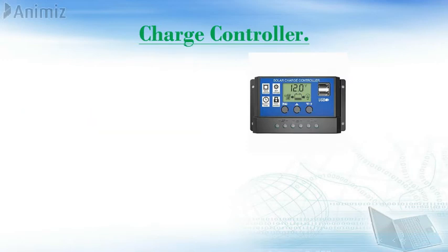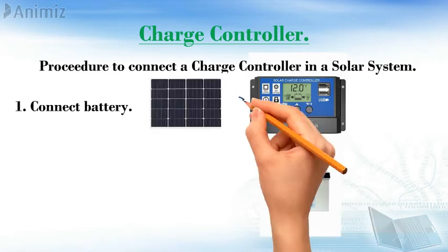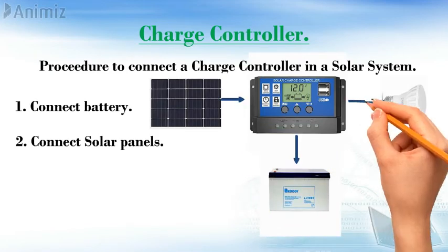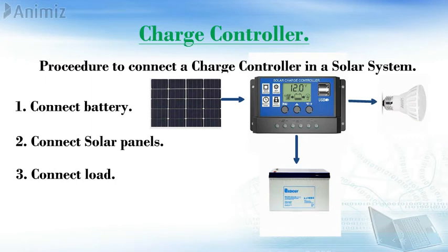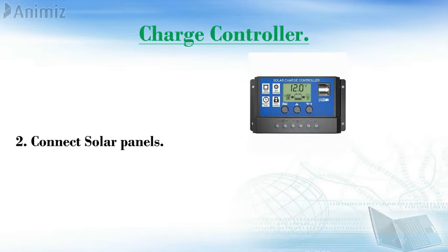Procedure when connecting this component into a solar system: connect battery first, solar panel, and then connect load. When disconnecting, start with the load, solar panel, and then disconnect battery.